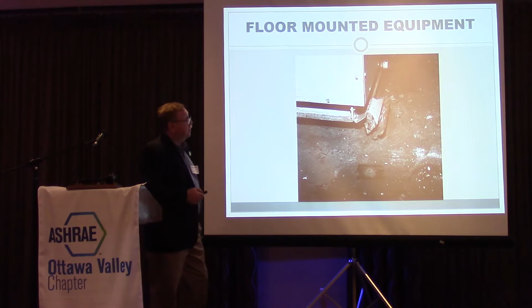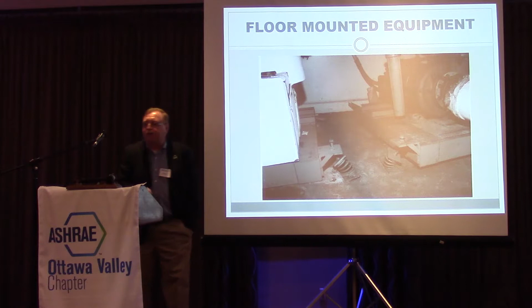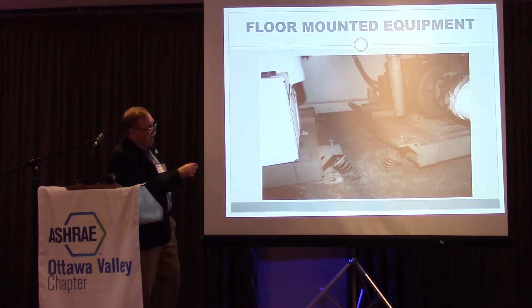I like to show this one because there was nothing on these—no seismic restraints at all. They bounced around but stayed in place, and the only reason is these were so old that the springs were welded to the top and bottom plates. I don't think any manufacturer today welds the springs in place; we put them in castings and things like that. Nobody does this anymore, but it was interesting because being so old, it worked—it stayed in place, bounced around, but ended up about where it started, give or take an inch or two.